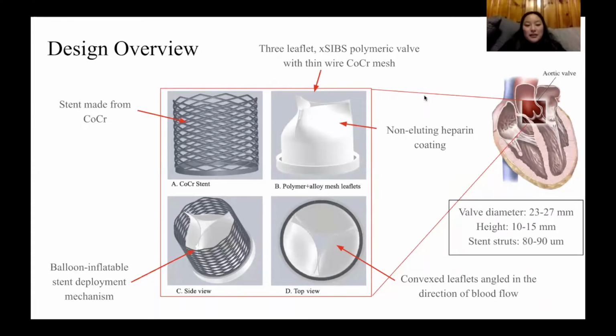The leaflets of the valve will have a thin cobalt chromium mesh embedded within and a cobalt chromium stent for balloon inflatable deployment. The leaflets will be convex and angled in the direction of blood flow to help minimize shear stresses that often lead to thrombosis and the effects of blood pressure. The polymeric material will have a 1% non-eluting heparin coating. The struts on the stent will be 80 to 90 micrometers to maintain strength and stability.